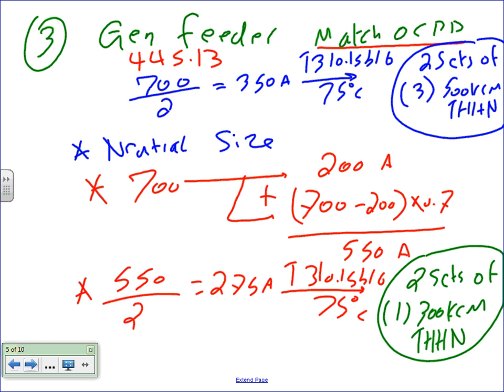That's it. Any questions, guys, about sizing the feeder phases? The generator feeder phases as well as the overcurrent device. Let's go to the grounding electrode conductor and the main bonding jumper. Can I move? Everybody's okay? Yes? No? Cool?